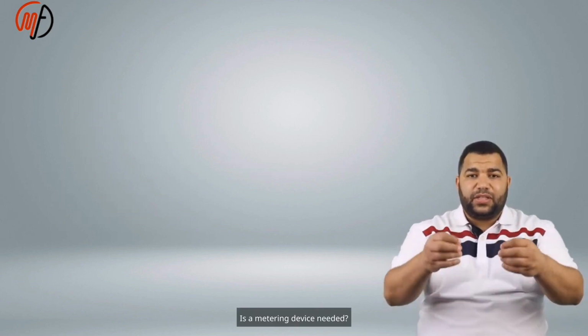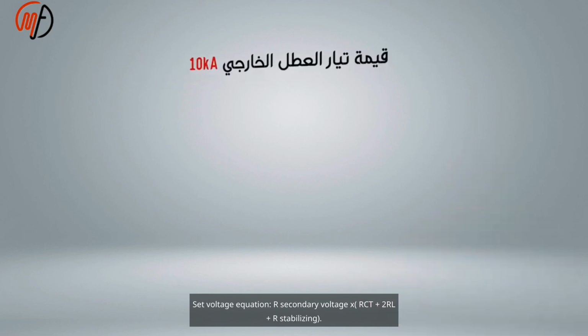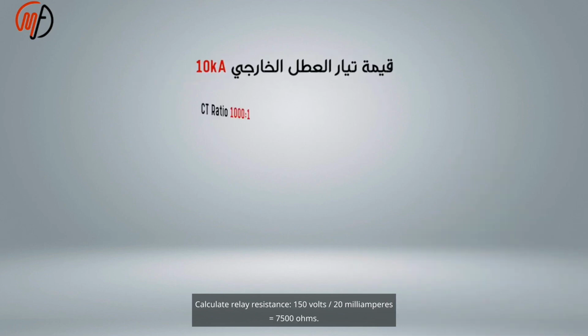Is a metering device needed? With 10 kiloamperes fault current and CT ratio 1000:1, check necessity. Set voltage equation: I secondary times (RCT plus 2RL plus R stabilizing). Calculate relay resistance: 150 volts over 20 milliamperes, or 7500 ohms.